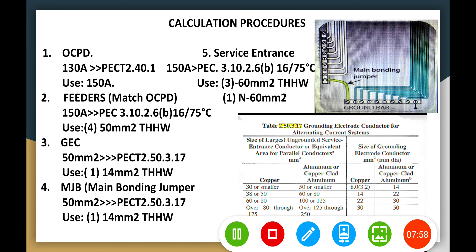For the feeder, as a rule of thumb the OCPD matches the wire sizing. We take the 150-ampere OCPD to PEC 310.2.6b16 at 75 degrees. For the wire sizing we get four 50 mm² TH-HW conductors including the neutral. For the grounding electrode conductor (GEC), based on the table, since we have 50 mm² from the main feeder and using copper, we use 14 mm² TH-HW as the grounding electrode conductor.